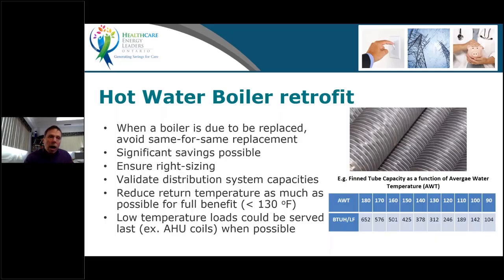Your load might have gone down. You may not need the same size. You may want to get a condensing boiler if it's for hot water. I'm not talking about steam here, but be very careful. A condensing boiler has 95% efficiency when the return water temperature is cold enough. You need a return water temperature well below 133 Fahrenheit. 133 Fahrenheit is where condensation may start to happen in a condensing boiler. You need fairly cool water.